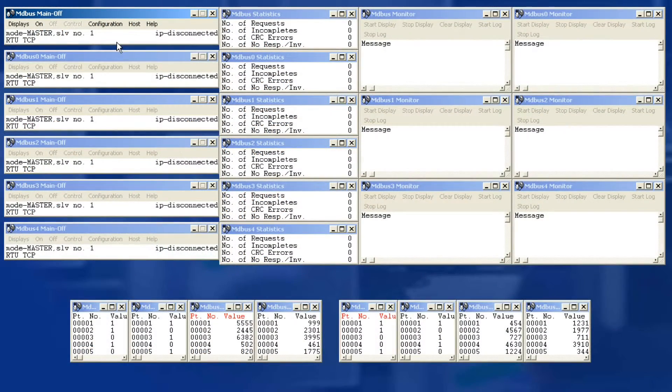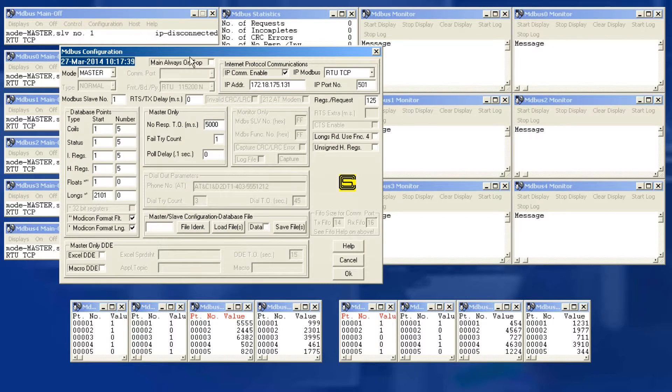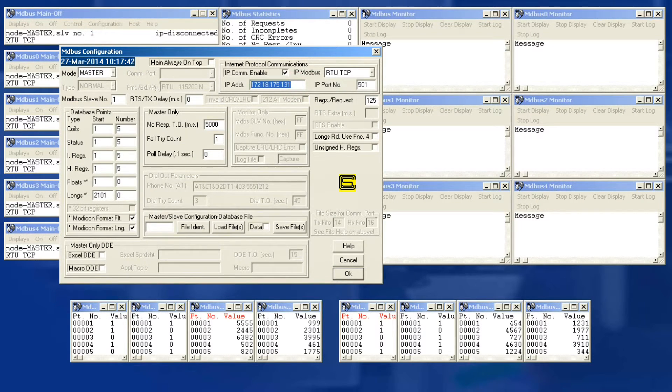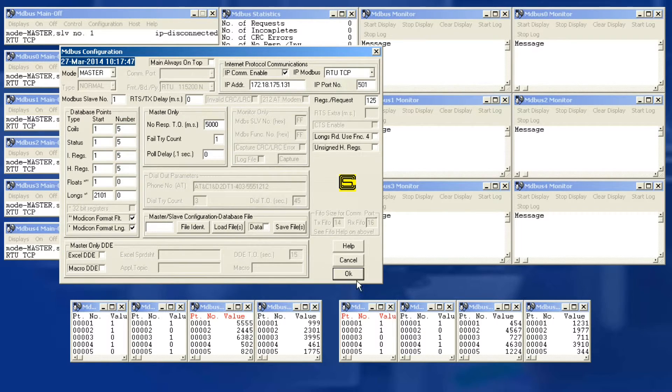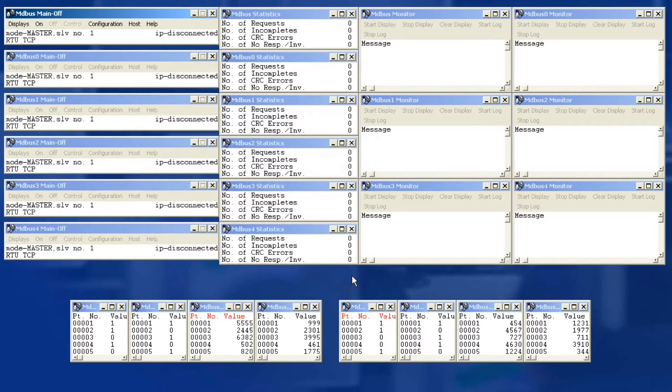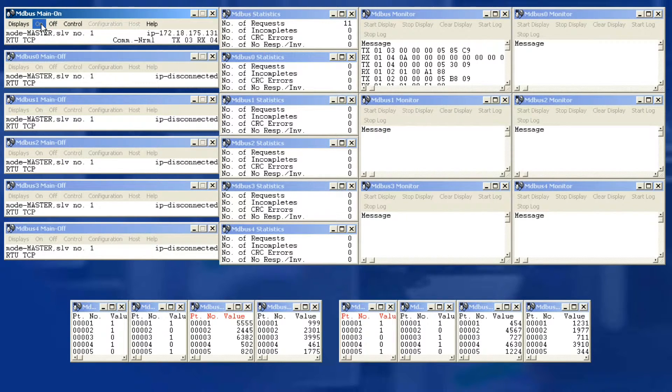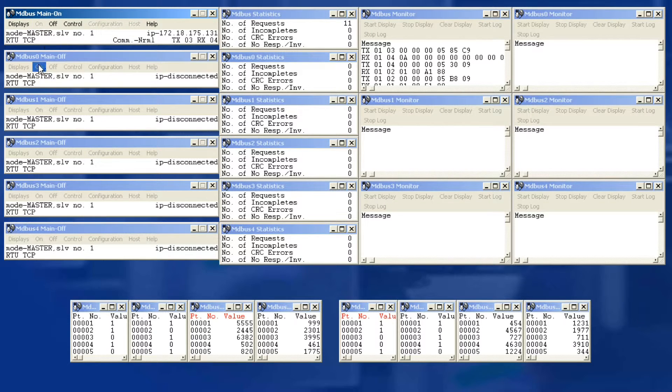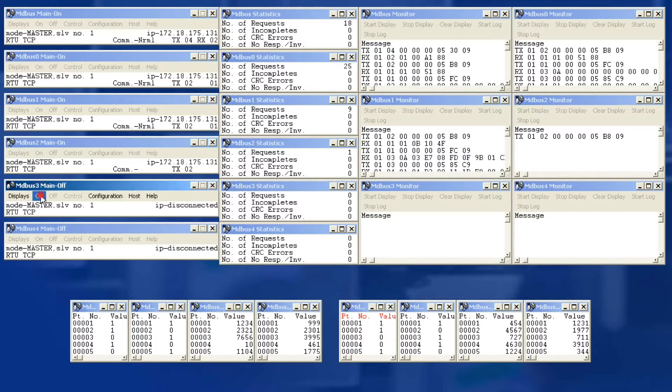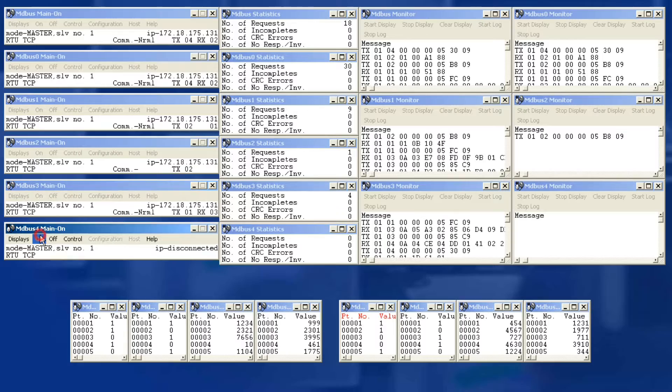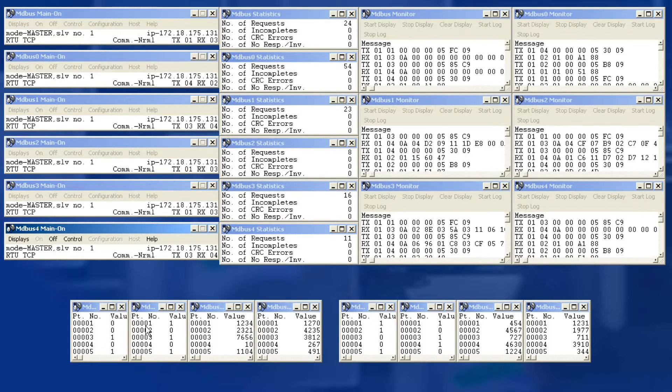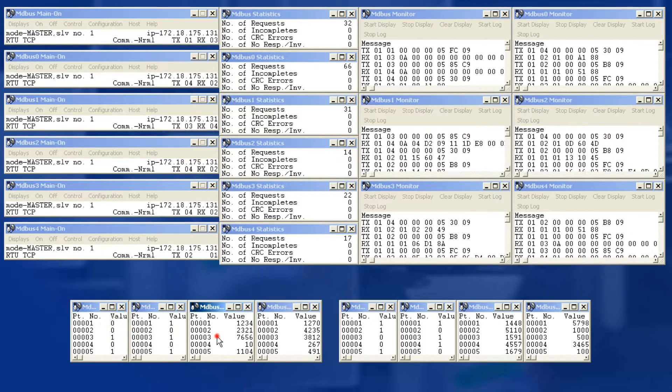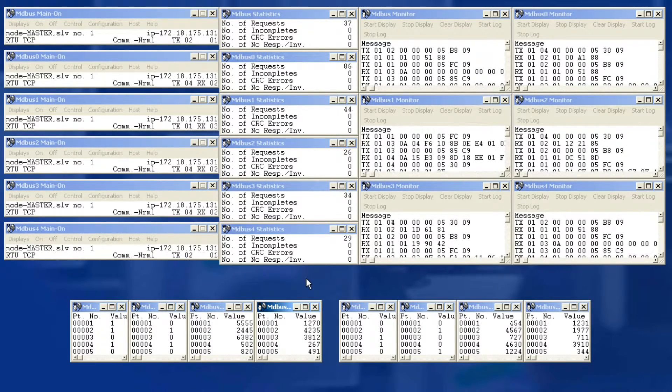Set up on the data center I have six master pollers. I've configured the master's IP address to the orbit's access point cell IP and the IP port number to what was configured in the port forwarding rules as the incoming port. Each master poller will have a different IP port number. Starting up the poller data begins to flow. Turning them all on simultaneously works as well and my analog and digital values from my poll devices are displayed below and are updating accurately.